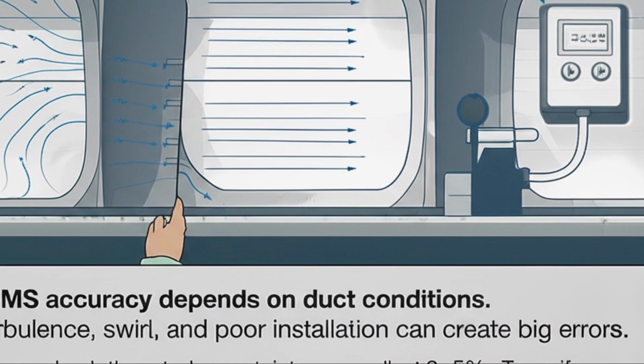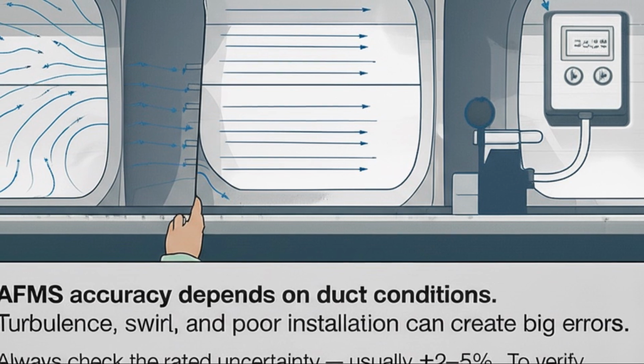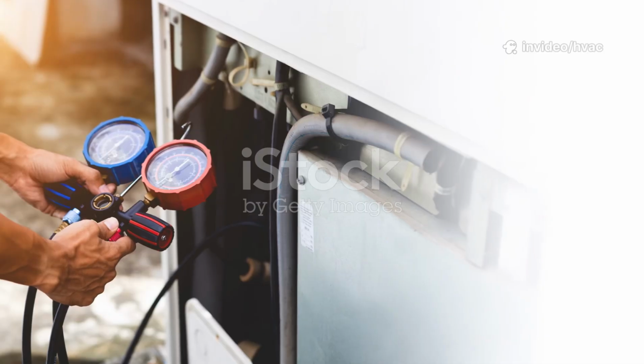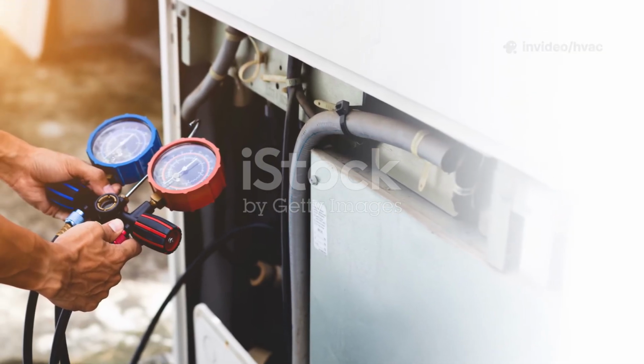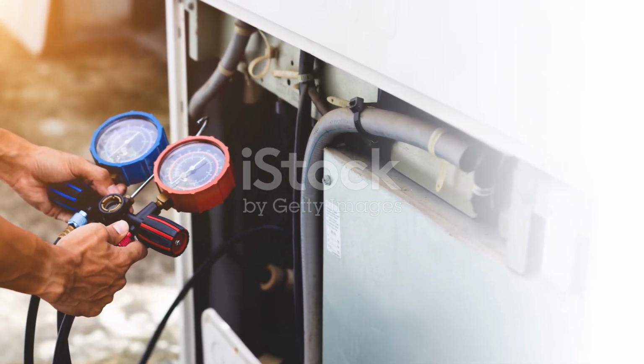AFMS accuracy really depends on duct conditions. Turbulence, swirl, and poor installation can all create pretty significant errors. Always check the rated uncertainty, it's usually around plus or minus 2 to 5%. And to verify, perform a manual duct traverse with a calibrated handheld device during commissioning.